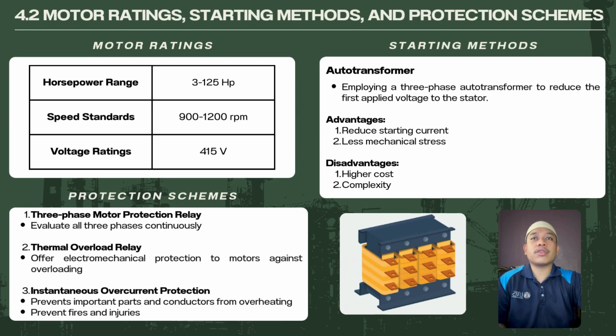Next, starting method. Auto transformer is the best choice for remote location. In this method, the motor starting current is limited by employing a 3-phase auto transformer to reduce the first applied voltage to the motor. The advantages are it reduces the starting voltage, which causes the starting current to reduce too. It also reduces the mechanical stress on the motor and load. On the other hand, the disadvantages are a higher cost and it is more complex to establish and maintain.